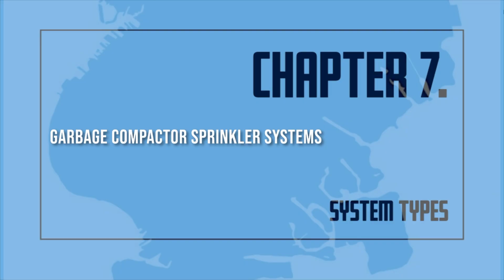Fire doors shall be installed in the chute to allow firefighter access to burning trash. The certificate of fitness holder shall know the location of all sprinkler heads, control valves, supply lines, and compactor rooms. A sketch of the entire compactor sprinkler system shall be drawn by the certificate of fitness holder. This sketch shall be posted in the compactor room, in a frame under glass. The sketch shall be made available to any representatives from the fire department.